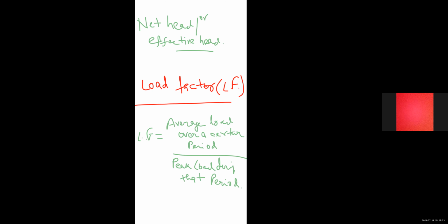If the area under a load curve is plotted, it represents the energy consumed in kilowatt hour, and the annual load factor may also be defined as the ratio of actual energy consumed during that year to the peak demand assumed to continue for 1 year.